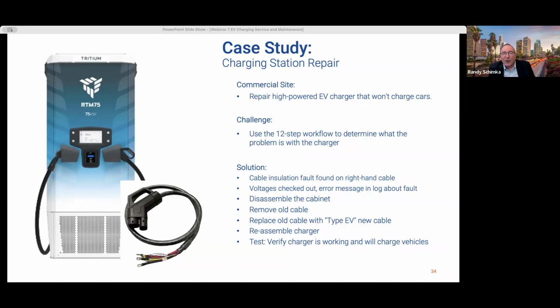Voltages were checked in the charger. The charger log had a cable fault error message, so that's a good clue. The cabinet was disassembled and the faulty cable was found and replaced with a compliant EV type cable, and the unit was put back together and reassembled and tested. So after testing, the charger was brought back online and everything was working okay. So this case study highlights the importance of quick diagnostics and using proper replacement parts to restore functionality.